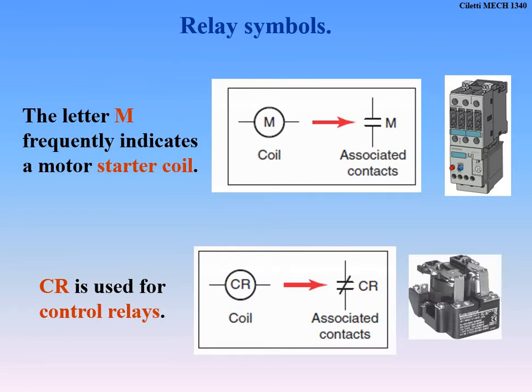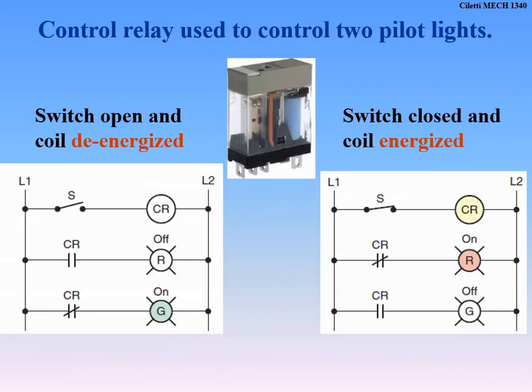In relay symbols, a circle shows up on our ladder logic. A circle with an M in it is a motor contactor or motor starter coil — though in Siemens it's a memory coil. CR stands for control relay, used for controls and different relays. These are the output coils on the right-hand side of the ladder logic. Normally open and normally closed contactors energize and de-energize to open and close things on the other end.